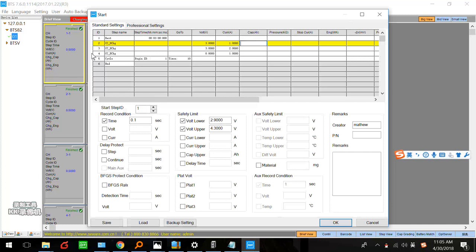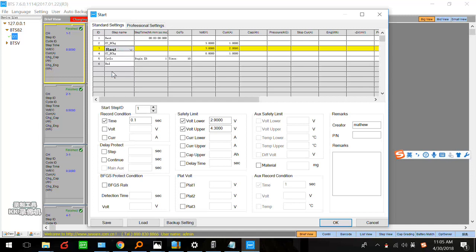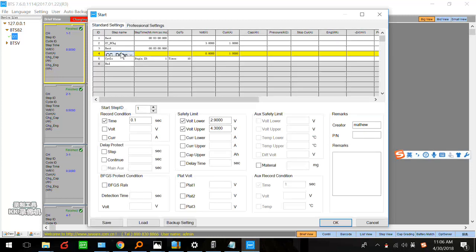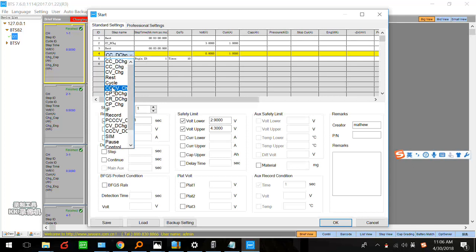Next, add a rest step after discharge, because after charging or discharging the battery temperature rises and we need to let it cool down — set three or five minutes depending on your needs. Then set a constant current and constant voltage charge step. Set the charge current, for example 1A, depending on your battery specification — it could be 2A or 0.5A. Set the stop current, for example 0.4A.